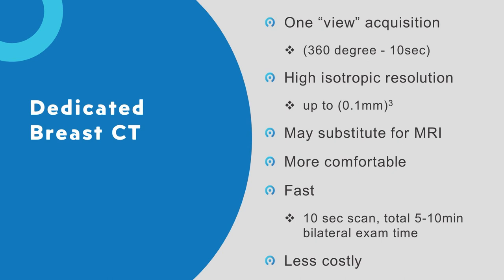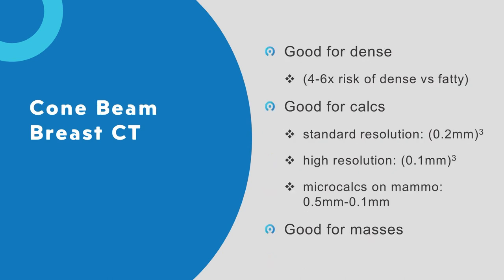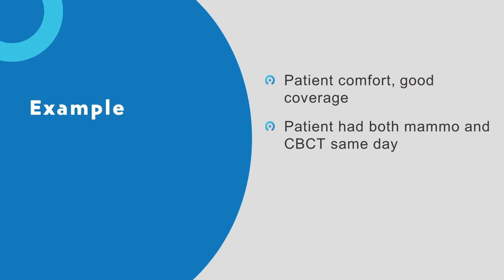The capabilities: excellent for dense breasts because there's no overlap, no compression — so all those false positives from compression overlap don't happen. Good for calcifications, since the standard resolution is 0.2 mm cubed and high resolution is 0.1 mm. This is perfect isotropic resolution in every direction — the same resolution in all planes. The unit of imaging is a tiny voxel measuring 0.273 mm, which can be improved with reconstructions. It's good for masses and also good for asymmetries.